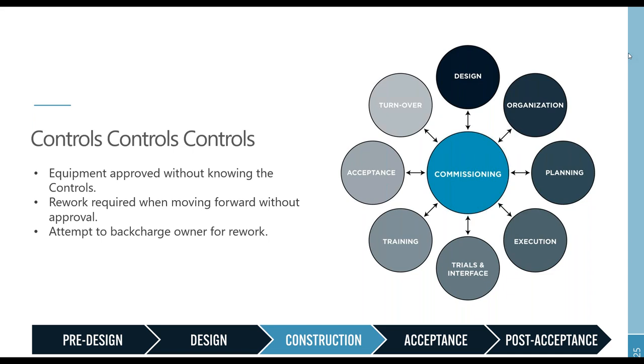Now, far too often we get documents separately. We get equipment already being approved without knowing how it's going to be controlled, especially on design build projects when the schedule is tight and things are just moving along out in the field. In order to try to meet very challenging milestones and goals for the project, in some cases things will get installed out in the field prior to them being approved, and in some cases equipment's going out there before we really have an idea of how it's going to be operated.